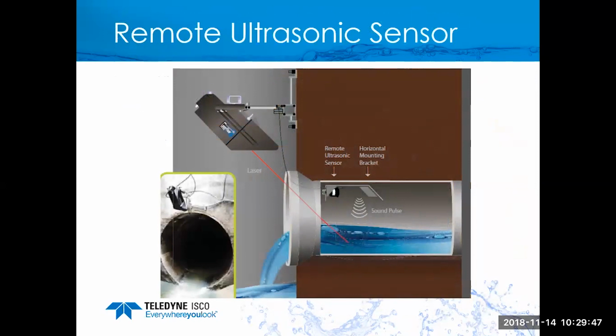So this does a couple things for you. One, it will allow you to read in these kinds of locations, but two, it will also improve your flow measurement method. And what I mean by that is your best flow calculation will be when you read the level and the velocity at the exact same location, and this accomplishes that.